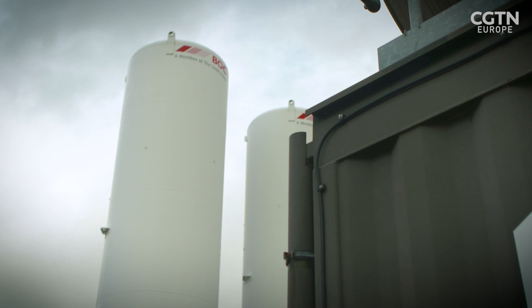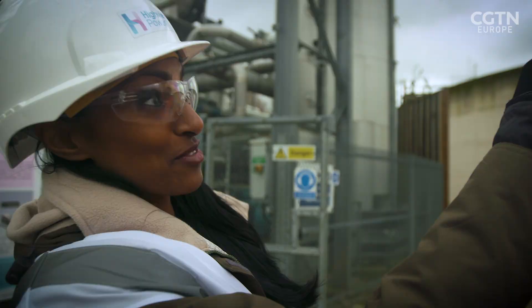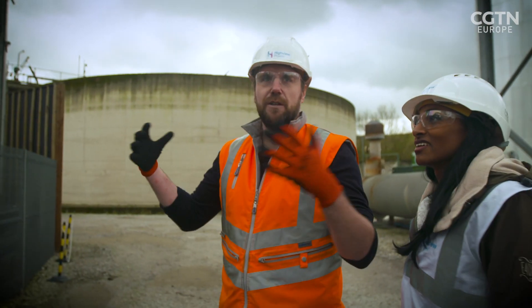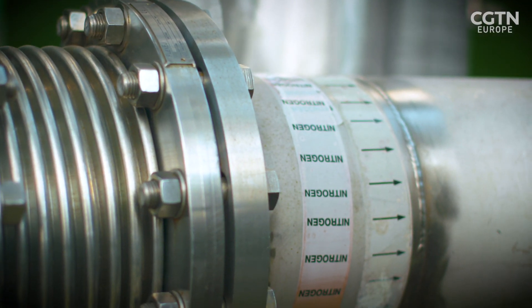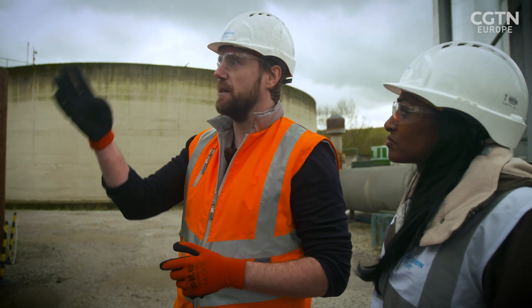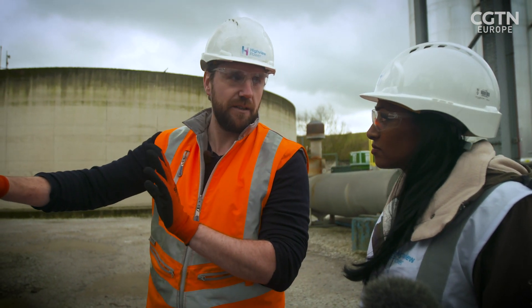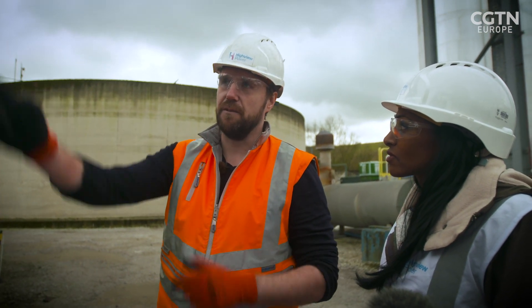Each tank is about 100,000 litres. So you've got extreme cold and extreme heat in those, coming together in the heat exchanger up there. They come together, massively expand, and send it into the turbo expander. It expands, and when it's in expansion it cools again. So the gas then comes out into another heat exchanger — we put more heat in. We do that four times through the four stages of the turbo expander. The turbo expander is then coupled to a generator, which converts that energy into electrical energy that we then export onto the grid.